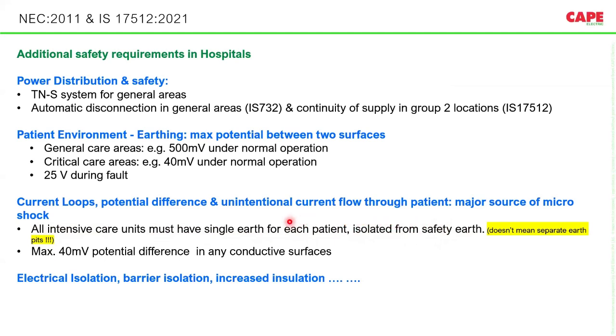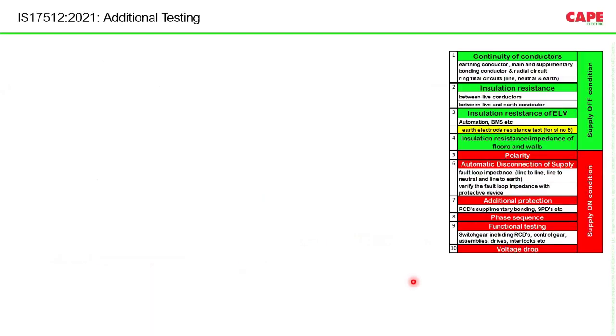It doesn't mean that you need to have a separate earth pit. The recommendation here is each single patient area, where you have an ICU, should have only one earth. That means a very good equipotential bonding must be made, and this can be isolated from safety earth. This is a kind of functional earth. We will discuss it maybe in another program, because this itself is a much bigger subject. Maximum 40 millivolt potential difference in any conductive surfaces must be maintained.